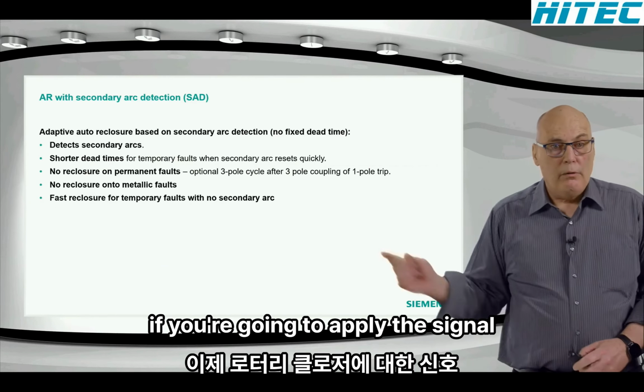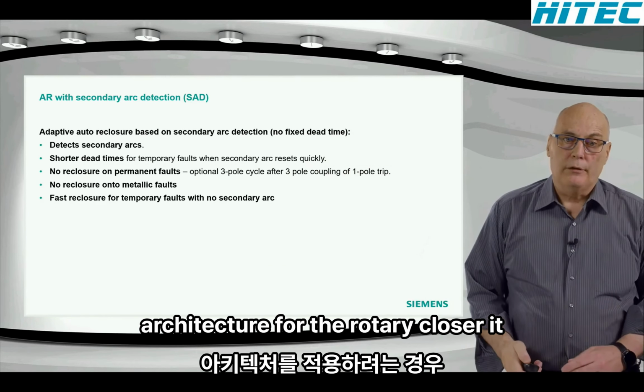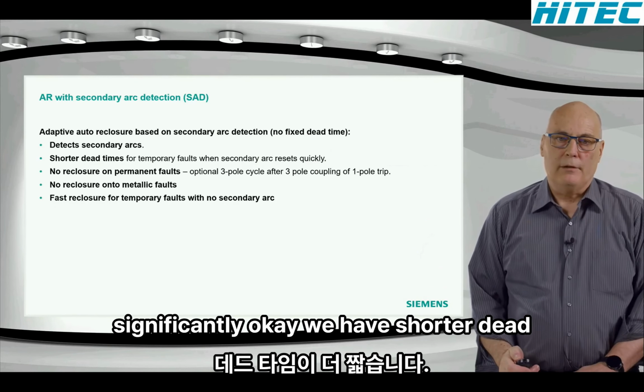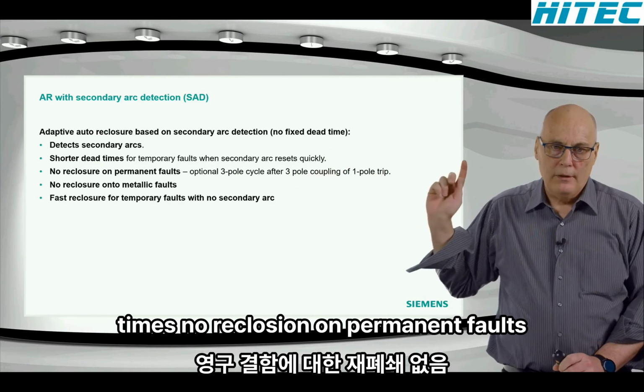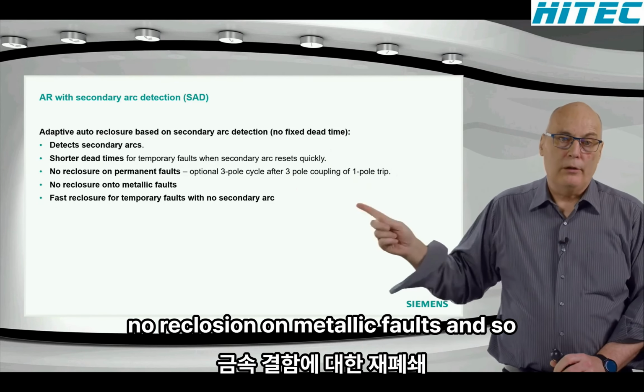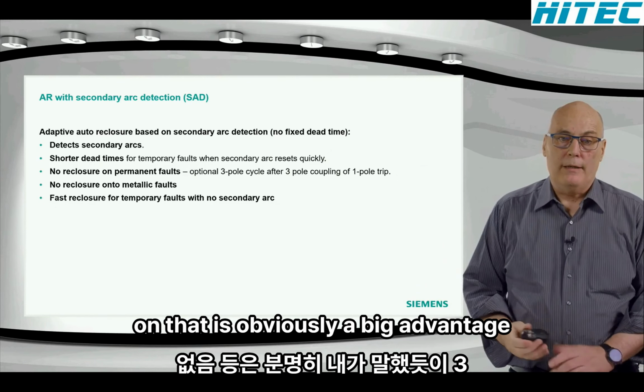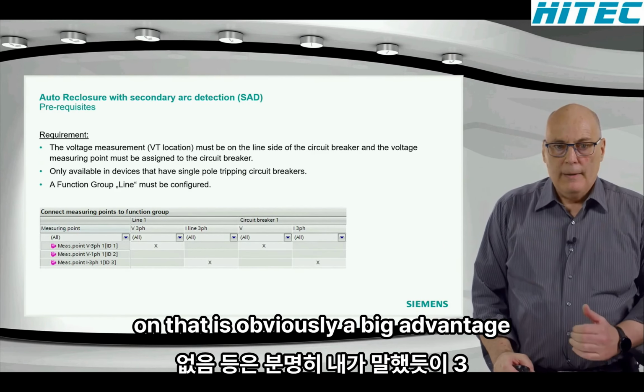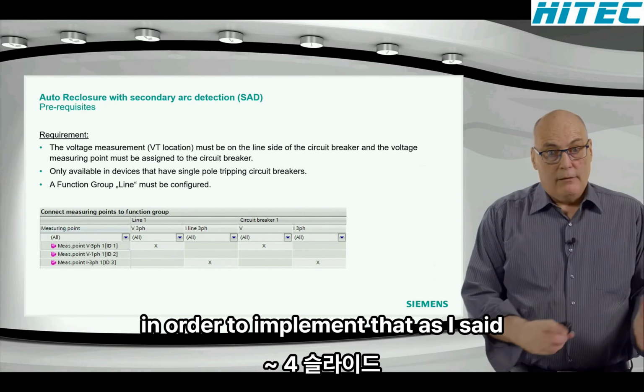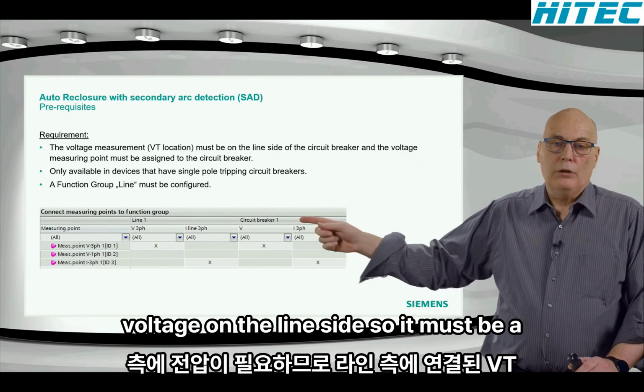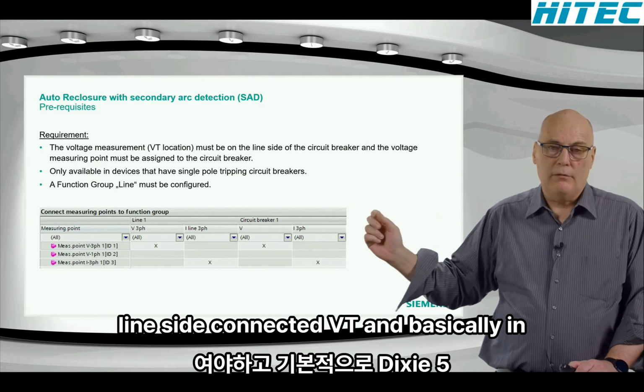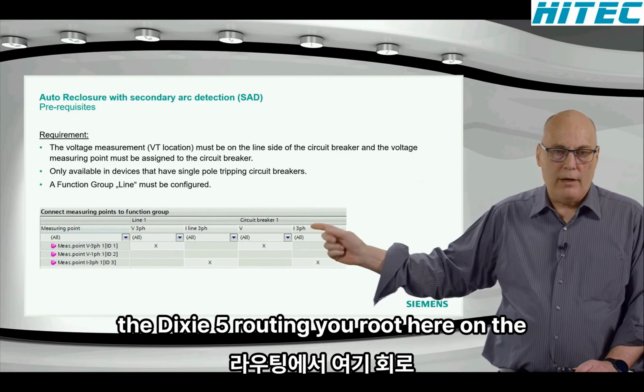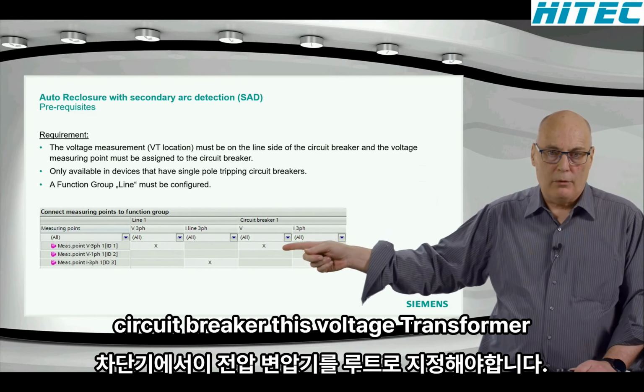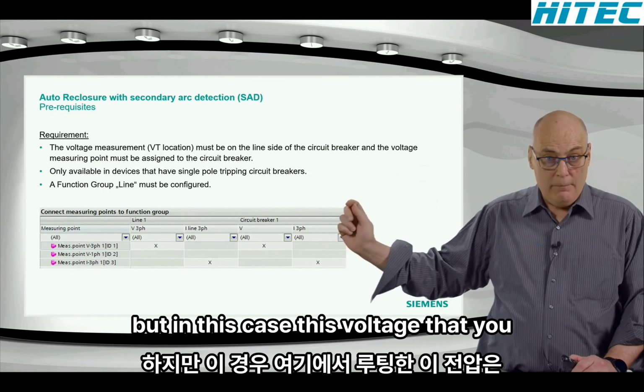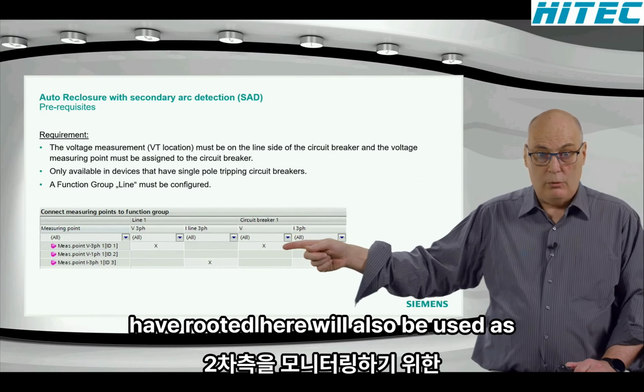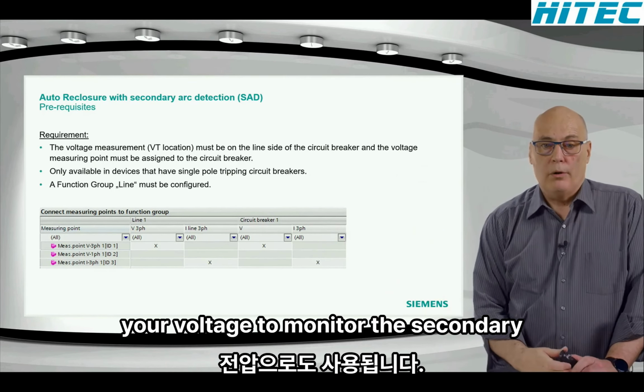So now, if you're going to apply the secondary arc detection for the auto recloser, it will improve the performance significantly. Okay, we'll have shorter dead times, no reclosure on permanent faults, no reclosure on metallic faults, and so on. That is obviously a big advantage. In order to implement that, as I said 3 or 4 slides back, we need the voltage on the line side. So it must be a line side connected VT, and basically in the DIGSI 5 routing, you route it here on the circuit breaker. This voltage transformer is typically for operational measured values. But in this case, this voltage that you have routed here will also be used as your voltage to monitor the secondary arc.